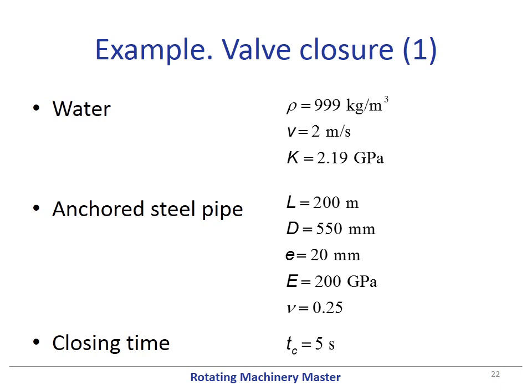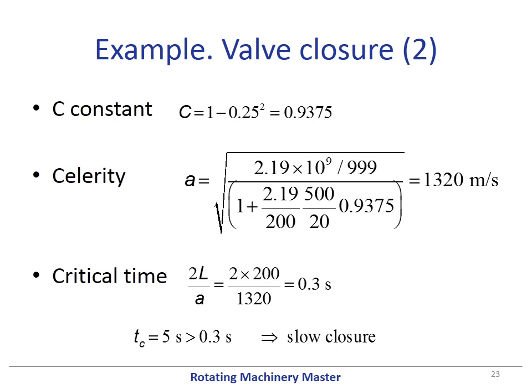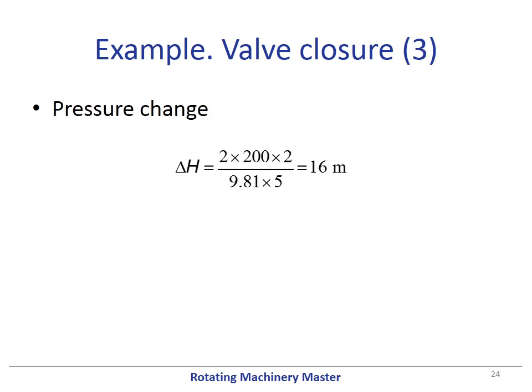This is an example of calculating the water hammer induced by a valve closure. Inside a pipe, we have water traveling at 2 meters per second. The pipe is an anchored steel pipe of 200 meters length. The closing time is 5 seconds. First of all, we compute the constant C for an anchored elastic pipe. Then we calculate the celerity and the critical time, which must be compared with the closing time. Since the closing time is larger than the critical time, the closure is slow. Therefore, the increase of pressure is given by Michaud's expression, resulting in 16 meters of column of water.